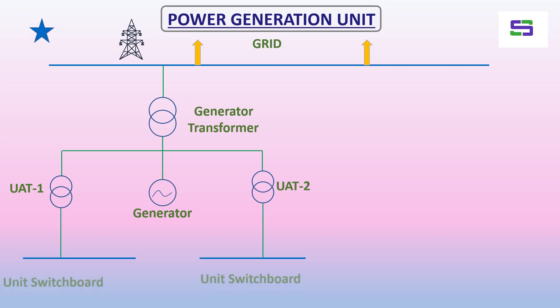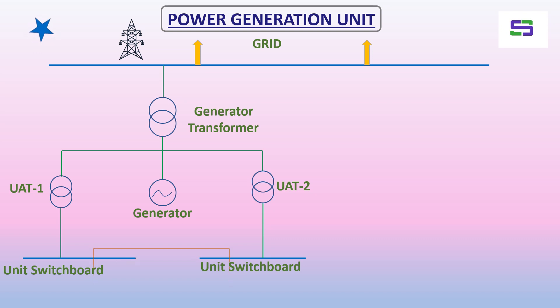It is stepped down to medium voltage switchgear — these are the unit switchboards — getting power from the unit auxiliary transformers, with a coupler in between the two switchboards. These are the unit arrangements. The auxiliary power system distribution further downstream will be distributed, but up to this medium voltage level — 11 kV or 6.6 kV — the unit switchboards are there.